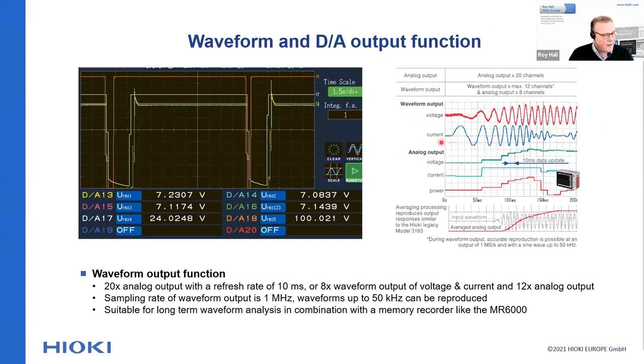It can be combined with an analog output, which basically is a trend information of the measured RMS values, as you can see here at the bottom. And the update interval for that is the same as the update interval of the display, and can be then at a minimum 10 milliseconds for the update rate. So when you are interested in long-term characteristics of your system, it might be interesting to connect these signals to a high-performance memory recorder, for instance, like the MR6000 of Hioki, and then you can get a long-term saving of your values and waveforms of the voltage and current, and use that for later analysis.